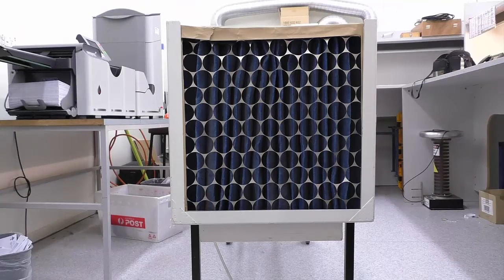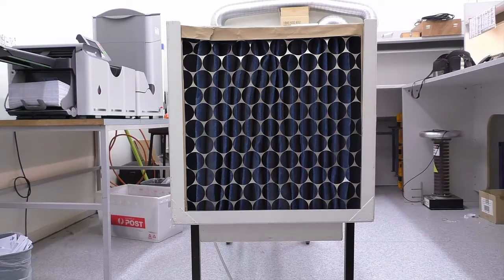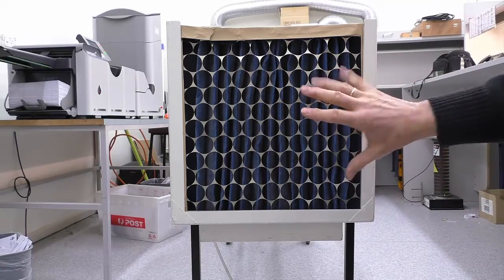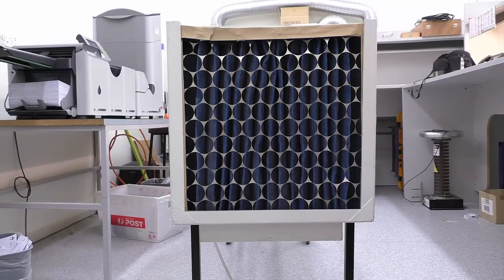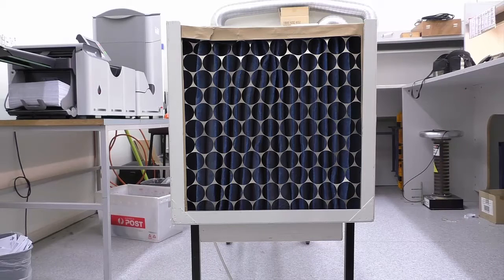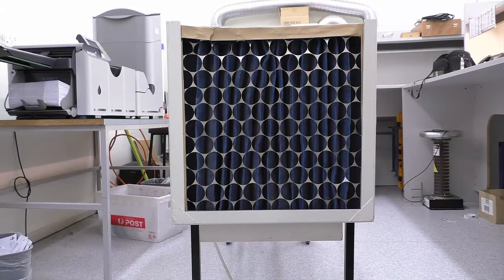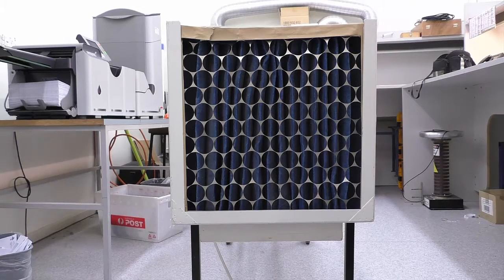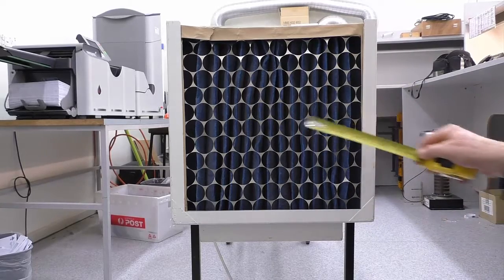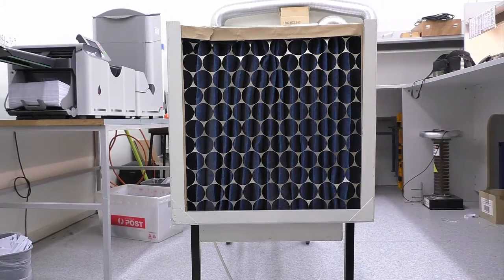Okay, this is the other end of our flow rig. Now we're going to measure the volume of flow that is being drawn in, which should be the same as the outlet there. It's 166 liters per second. So in order to use the meter to do this, it can do all the calculations for us, except we've got to enter the cross-sectional area of this inlet.